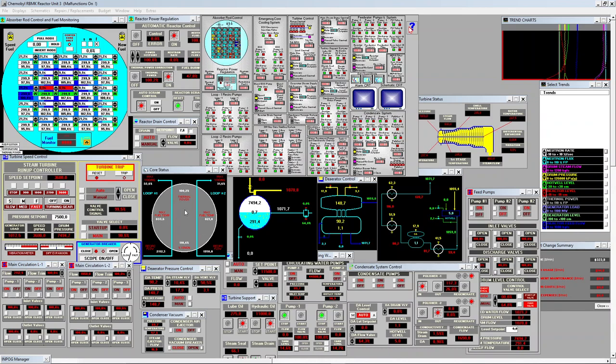Among other things, one of the design features of the reactor says that at all times you should have the equivalent of 15 rods inserted into the reactor to keep controllability. So with less than 15 rods inserted, you lose the controllability because you rely too much on boiling to create reactivity, which is not safe because in front of a critical runaway, the rods that you have left within the reactor core are not enough to control it, which is what happened in the accident in Chernobyl Unit 4. Well, there was a cascade of things, but basically this was one of the main design features that led to the accident.